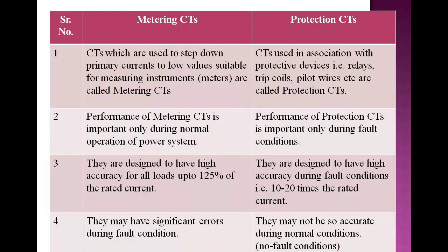Here is the comparison between metering CTs and protection CTs. CTs which are used to step down primary currents to low values suitable for measuring instruments are called metering CTs. CTs used in association with protective devices — that is, relays, trip coils, and pilot wires — are called protection CTs.